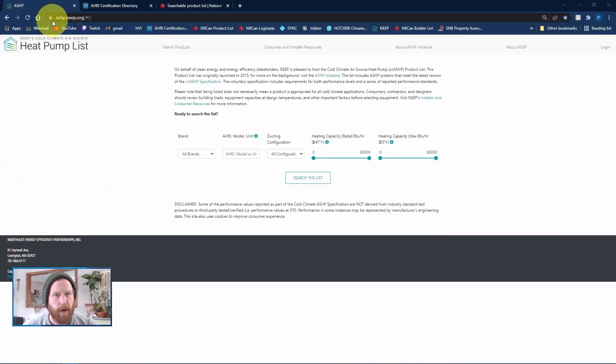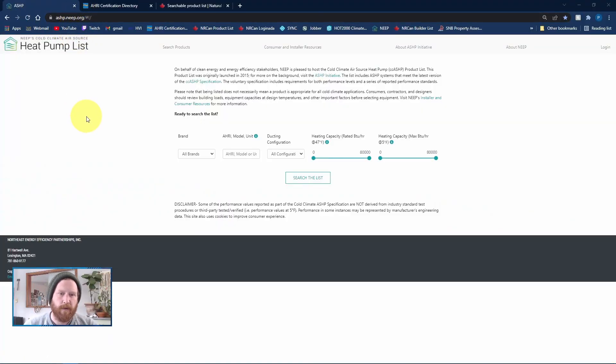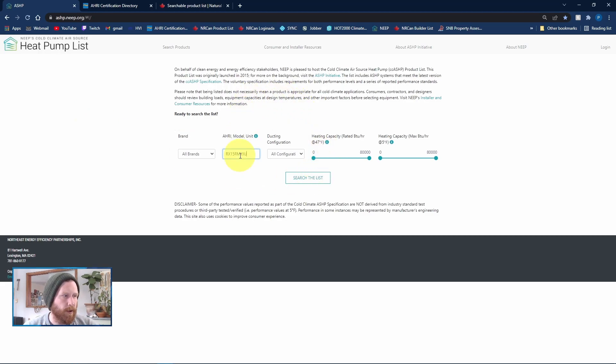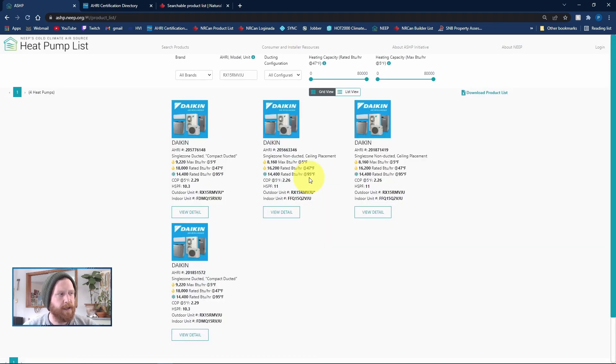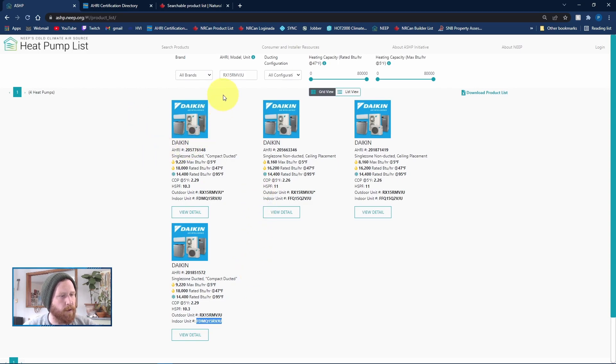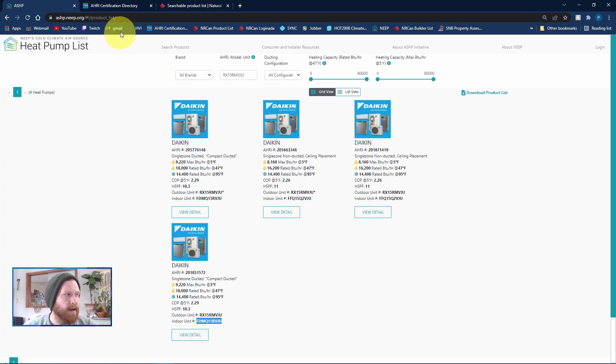So this is the NEEP website. You always want to check this one first because if it's on this website, it's going to be considered a cold climate heat pump and you're going to model it differently. But basically you just come here, search your model number. You already have the AHRI number. You can just put that in, search the list, and then here you can see we've got four options for this particular heat pump. If you search for your heat pump and it doesn't show up on this list at all, then it's not cold climate.